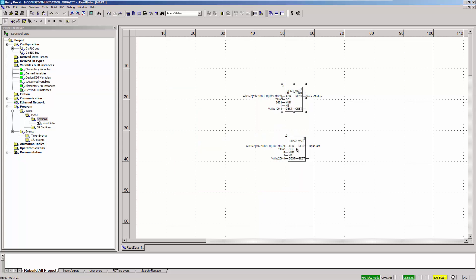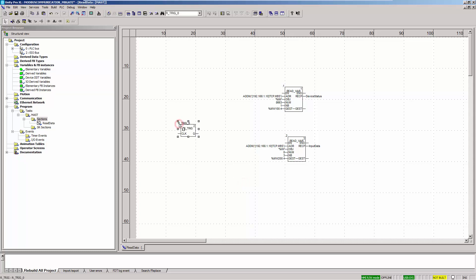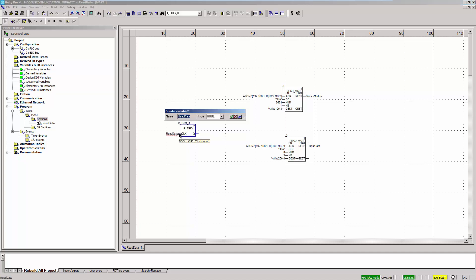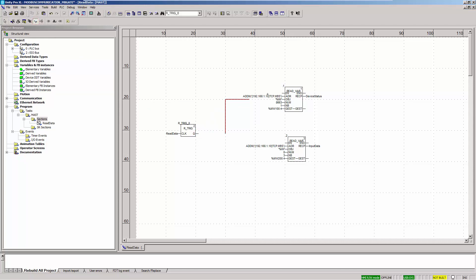To execute the two READ_VAR functions once, activate the optional input EN in both functions and add a function block R_TRIG. For the input of the function block, a variable is defined and the output is connected to the input EN of the two READ_VAR functions. Both functions are executed once as soon as the input of the R_TRIG function block is set to 1.